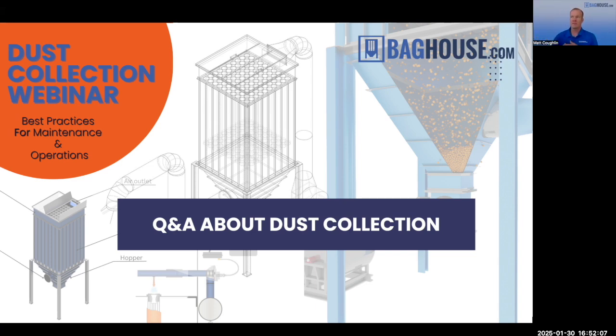Now, that disclaimer aside, there's a few basic requirements for all dust collection systems handling combustible dust. Typically, that would be explosion vents or venting on the baghouse itself, some sort of isolation between the baghouse and the process, so an isolation valve on the inlet or dirty air side of the baghouse.